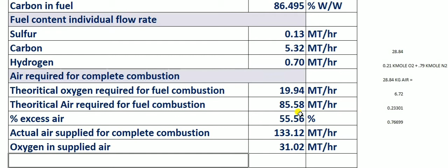Same formula, 0.23301 will give you the oxygen. So excess oxygen in flue gas, you want to calculate it, right? Excess oxygen in flue gas, that is how much we supplied, how much is consumed, remaining is 11.08, the excess oxygen in the flue gas. Simple stoichiometric calculations, no need to worry, it is going long, the video like that. Simple stoichiometry combustion calculation only.